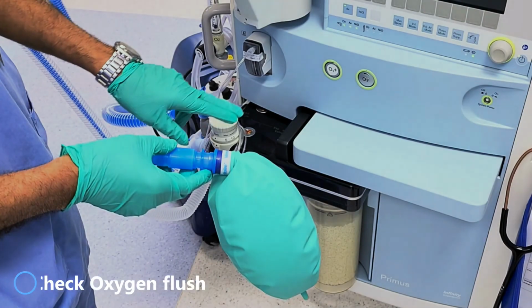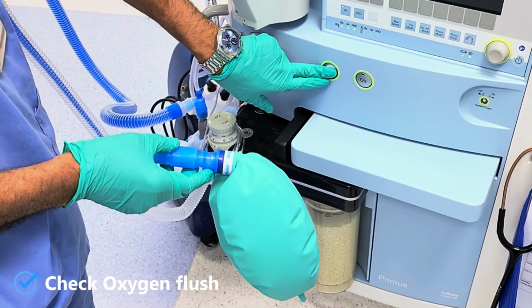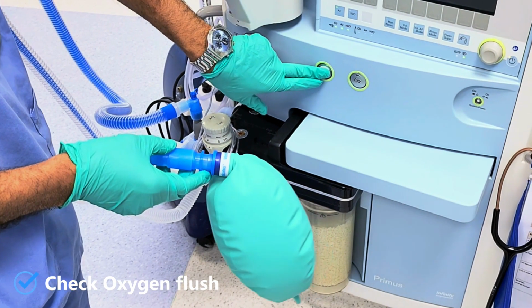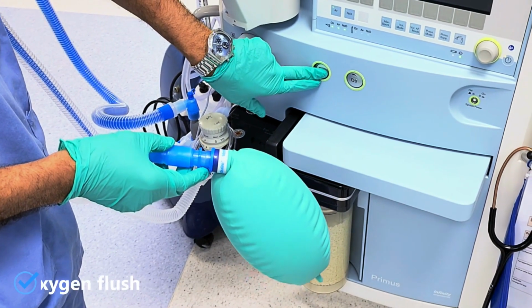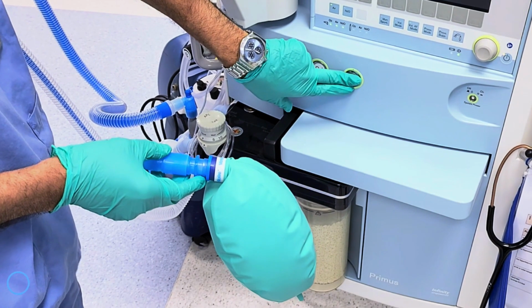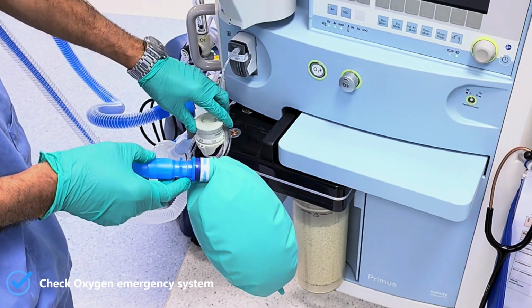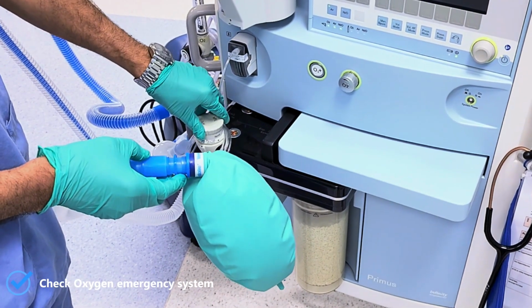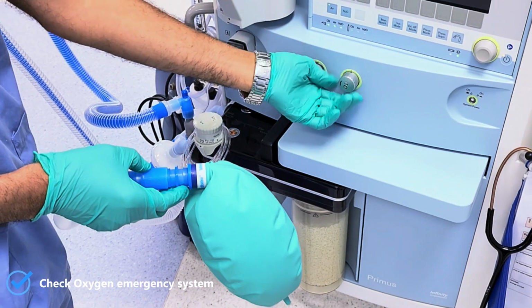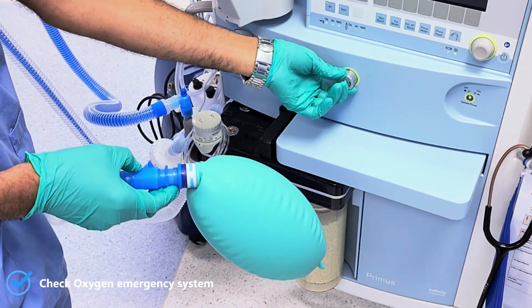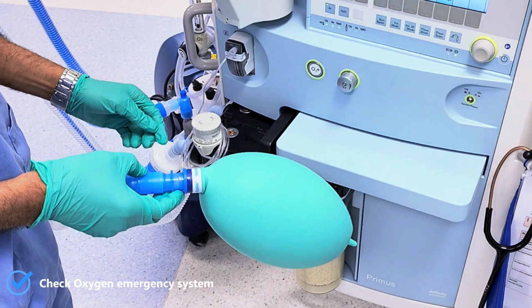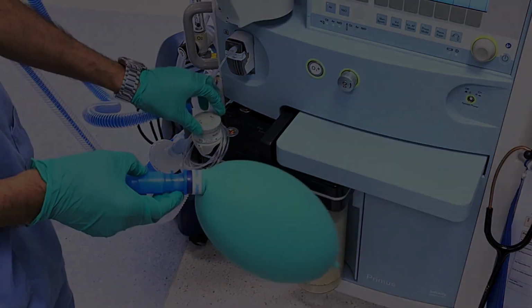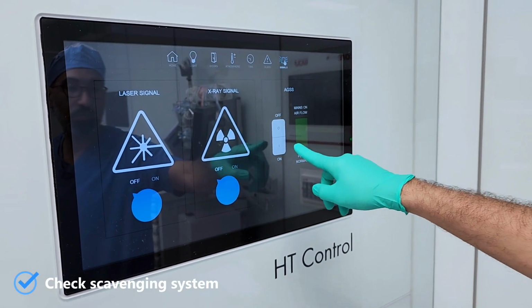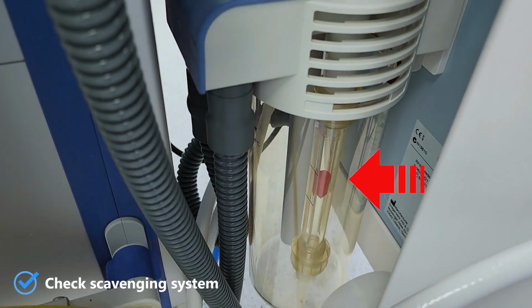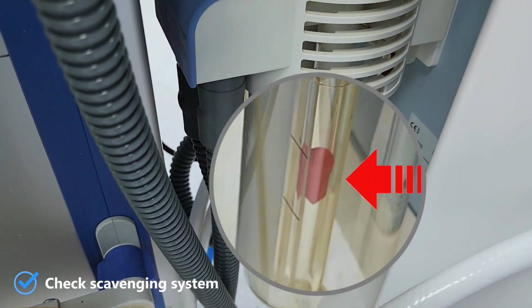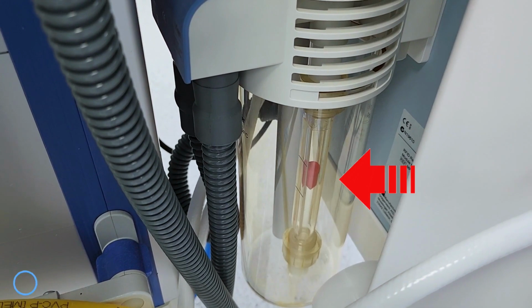To check the oxygen flush button, occlude the breathing circuit, activate the oxygen flush valve, and see that the reservoir bag is getting filled. Check the oxygen emergency delivery system: close the APL valve, occlude the breathing circuit, activate the oxygen emergency delivery system, and see that the reservoir bag is getting filled. The scavenging system has to be switched on from the main panel on the wall, and see that the bobbin behind the anesthesia machine is floating between these two black lines.